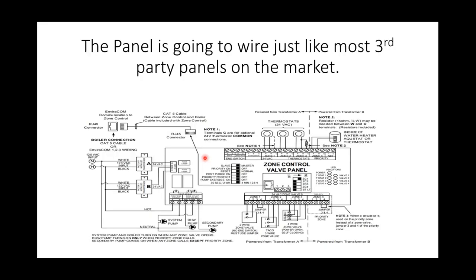So the panel wiring, again, is going to be just like most third-party panels, whether it be Taco, Argo, Honeywell. I think even Caleffi now has their own zone panels. It's basically the same way. We're going to use our CAT3 cable, and it comes with the boiler with the panel, so you don't need to source one. It's approximately 25 feet, and it'll plug right in.